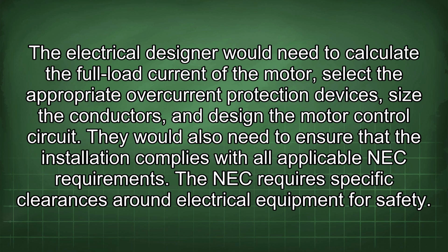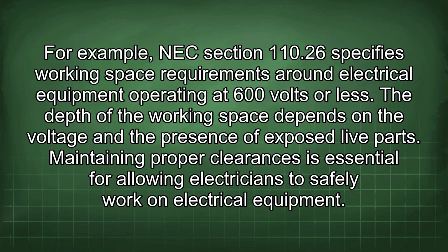The NEC requires specific clearances around electrical equipment for safety. For example, NEC Section 110.26 specifies working space requirements around electrical equipment operating at 600 volts or less. The depth of the working space depends on the voltage and the presence of exposed live parts. Maintaining proper clearances is essential for allowing electricians to safely work on electrical equipment.